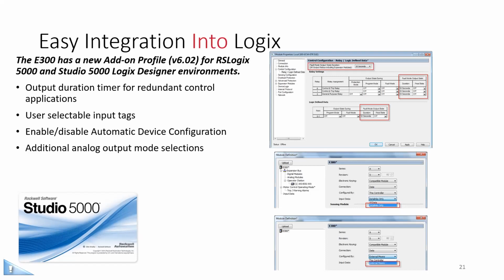So you make it a little bit more customizable and easy for you to read and interpret. You can also enable or disable automatic device configuration. So if a user would rather make and maintain configuration changes using the diagnostic station or the web server, you can just turn off the automatic device configuration so that it does not interfere with your configuration process.